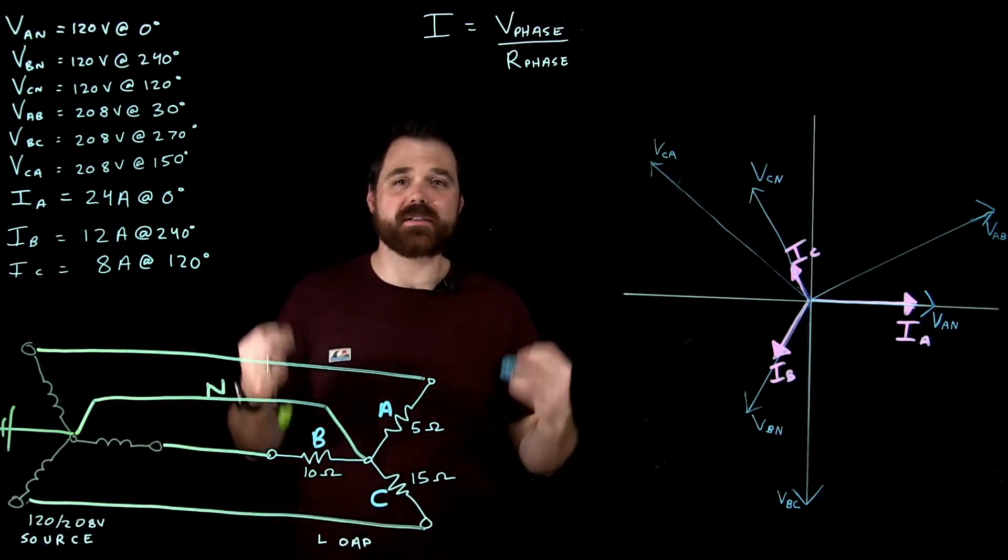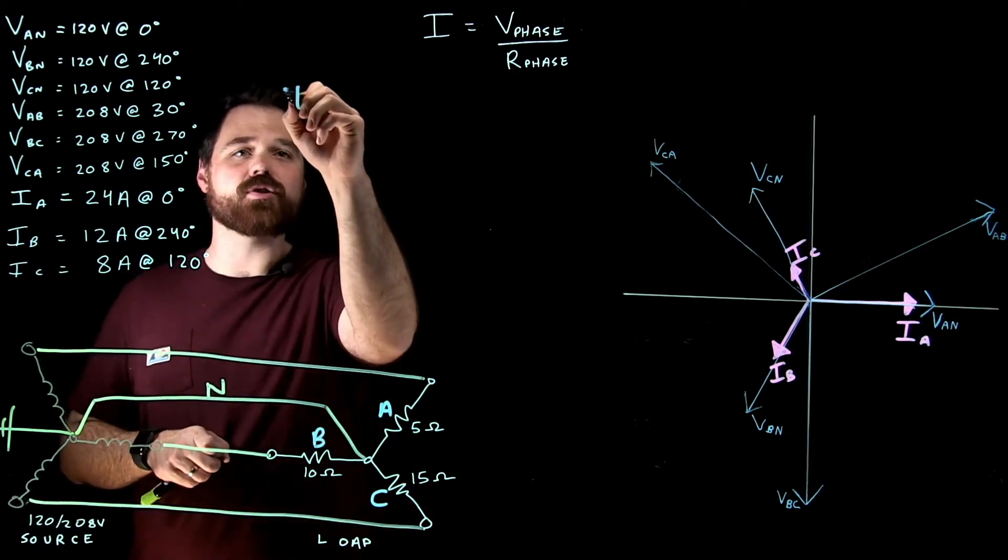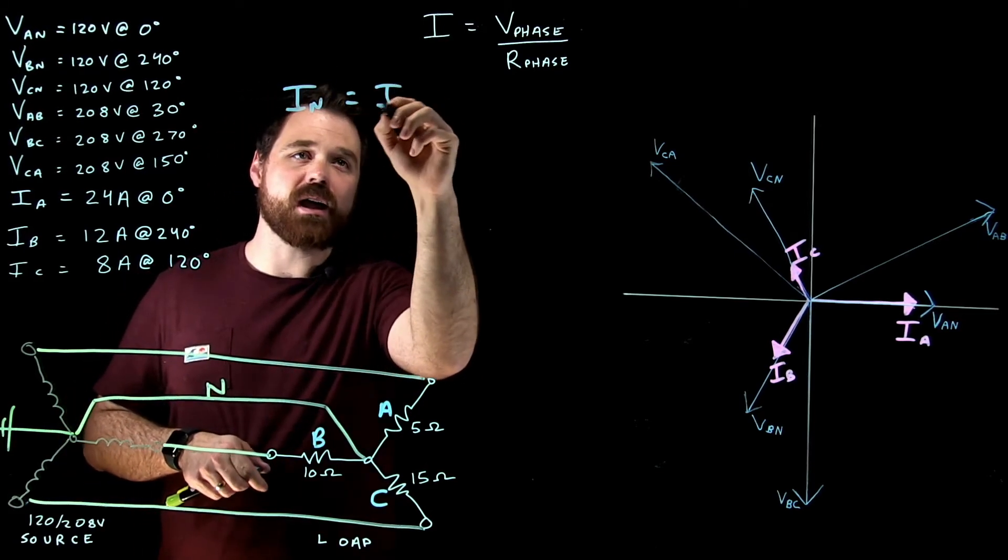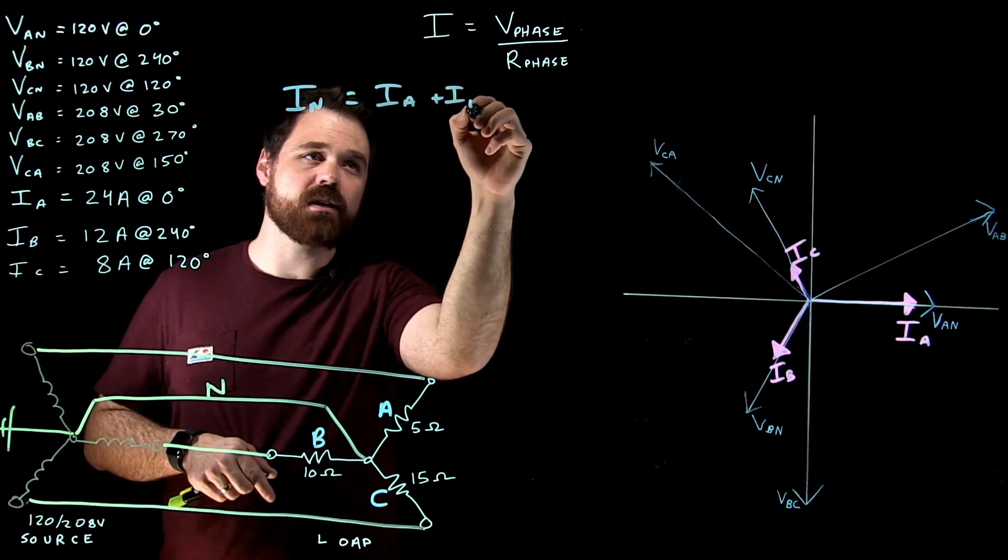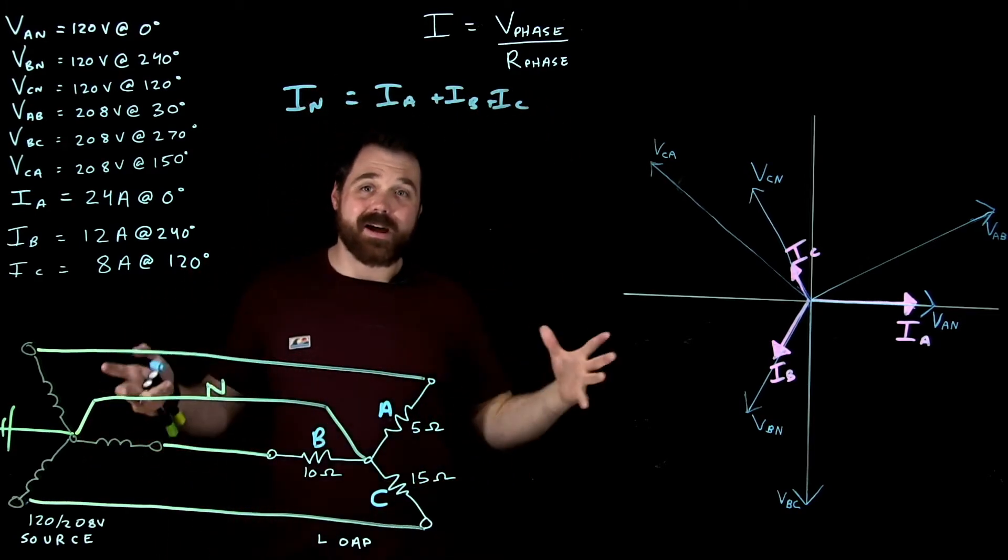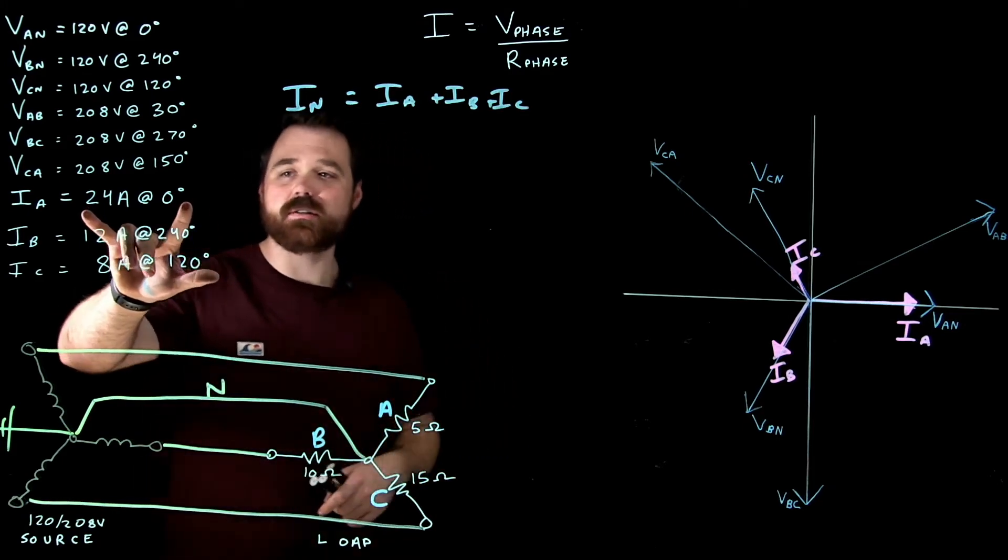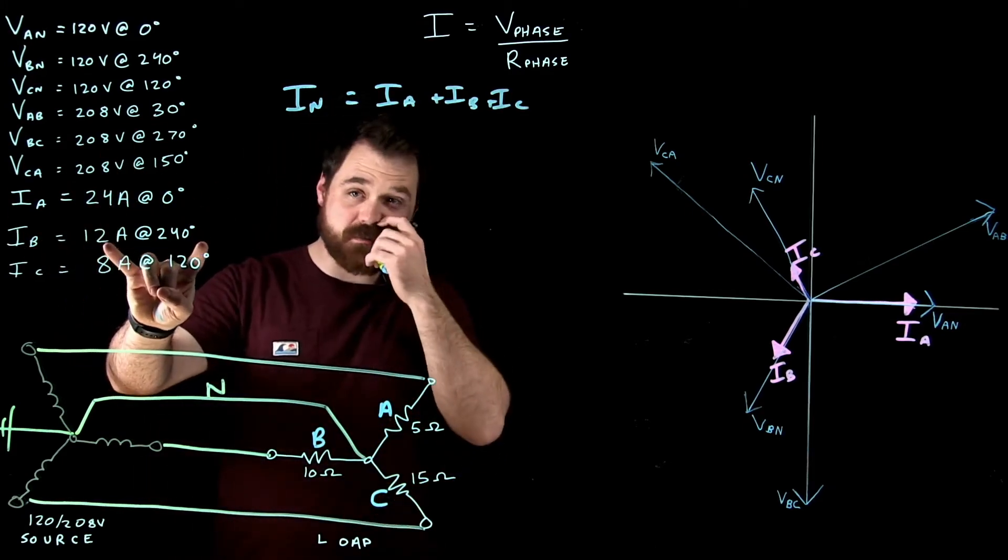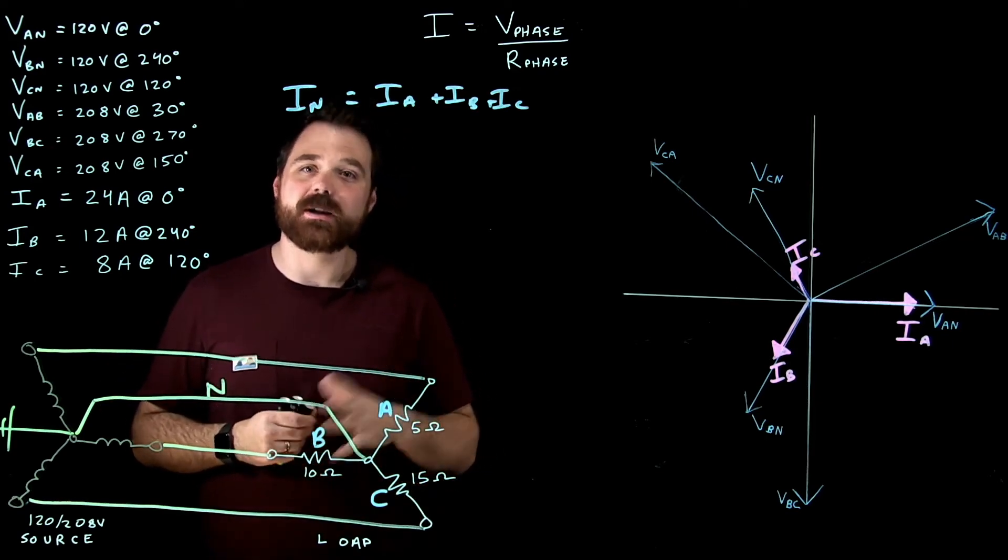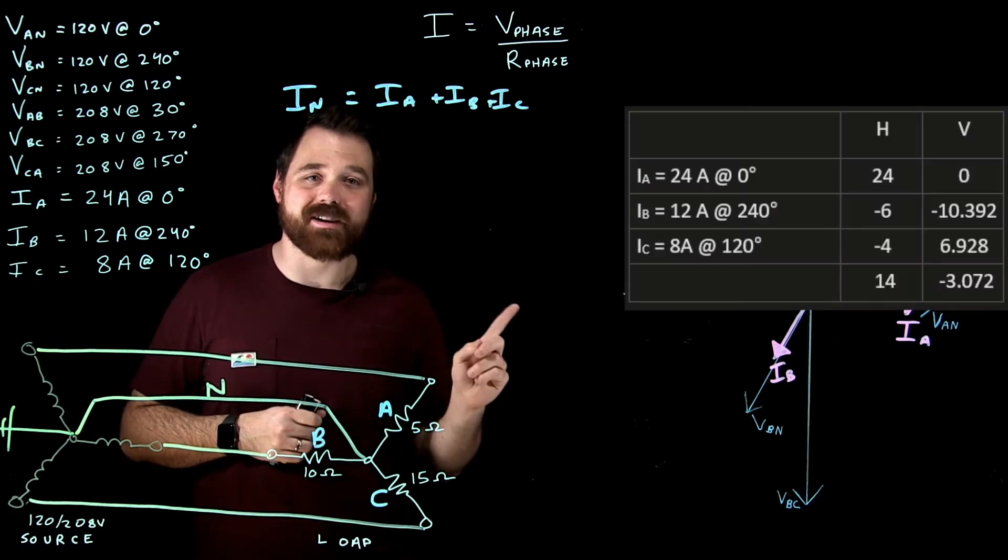So the trick with calculating the neutral current is that I neutral equals IA plus IB plus IC. Now what we end up doing is I end up taking these phasors. 24 amps at zero plus 12 amps at 240 plus 8 amps at 120. And I put them into an HV chart. And I add up all the horizontals, and I add up all the verticals.